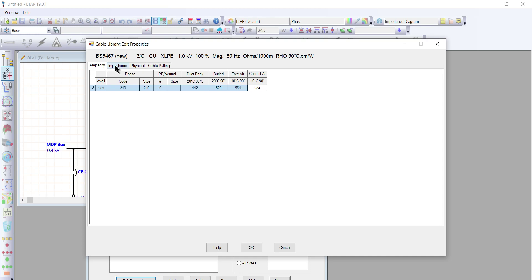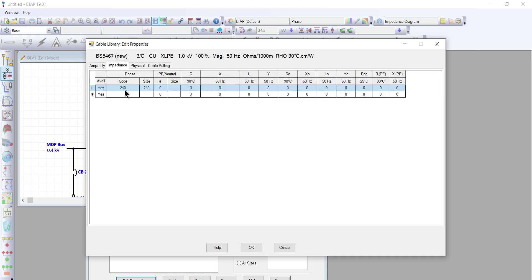Let's go to the impedance of the cable. We have the 240 mm² size already provided. We'll fill in the resistance at 90 degrees: 0.097. The reactance at 50 Hz will be 0.072. The inductance is 0.00023. The admittance will be 0.000156.